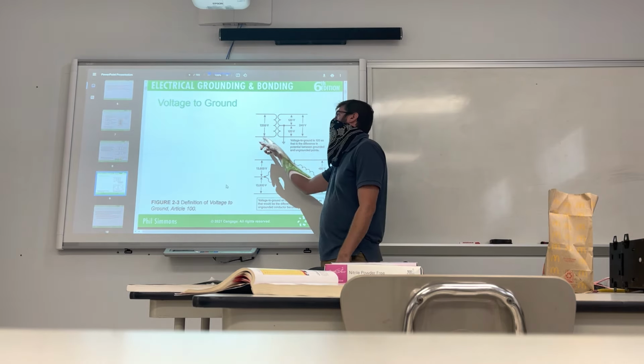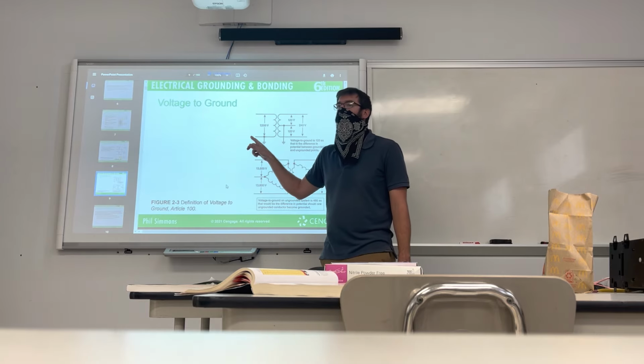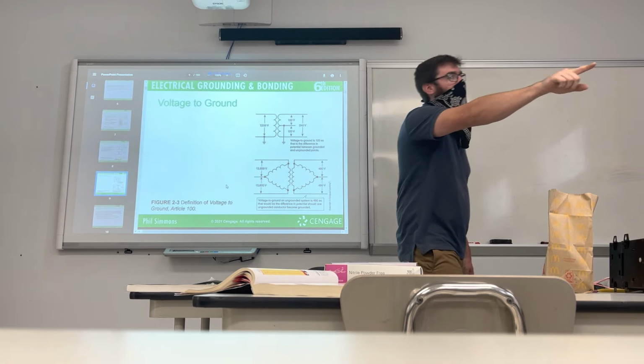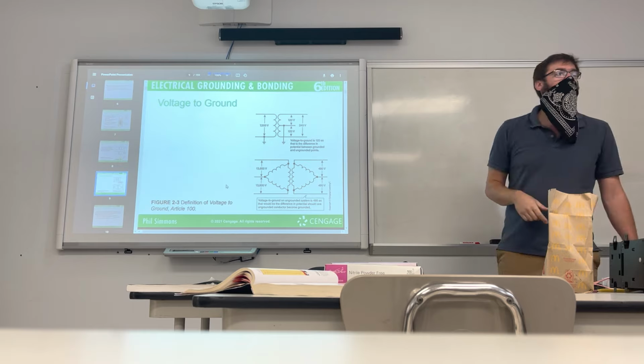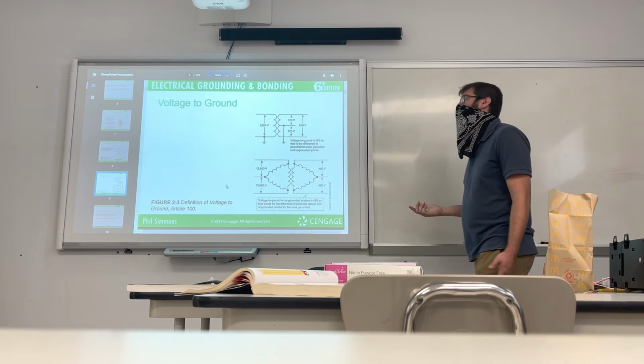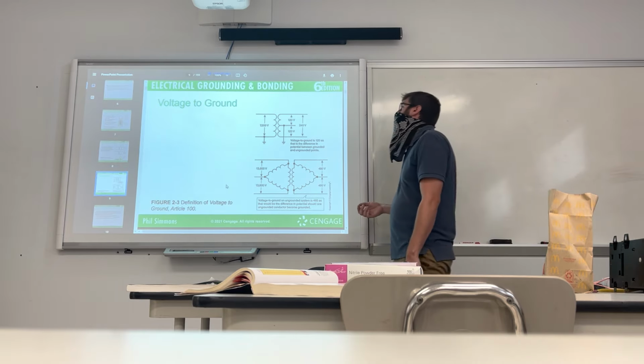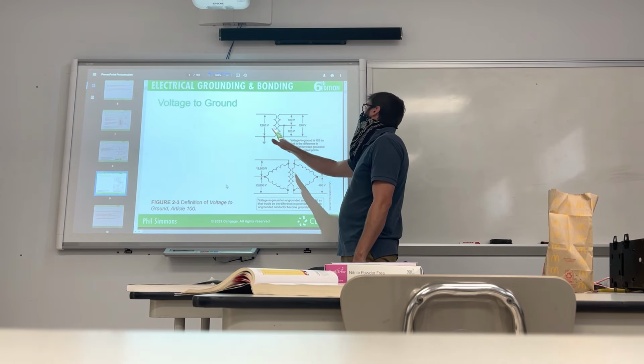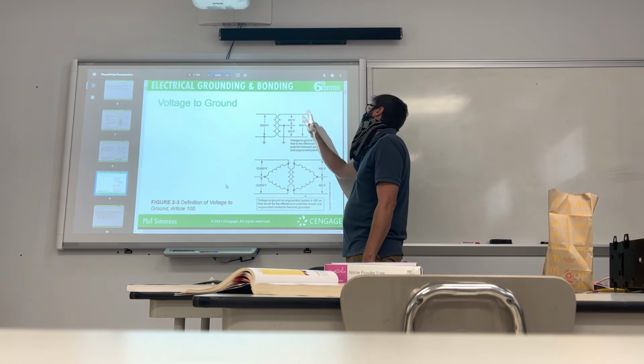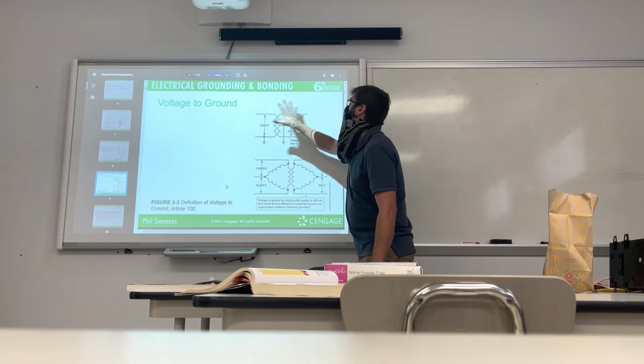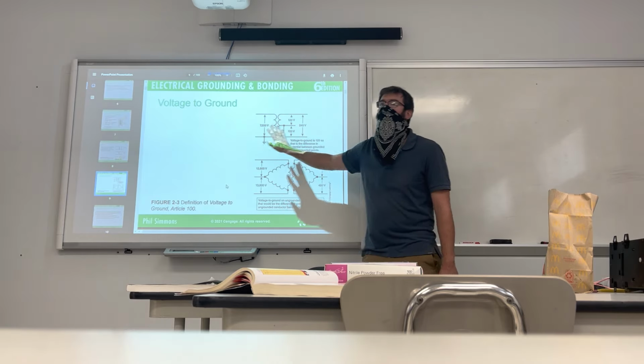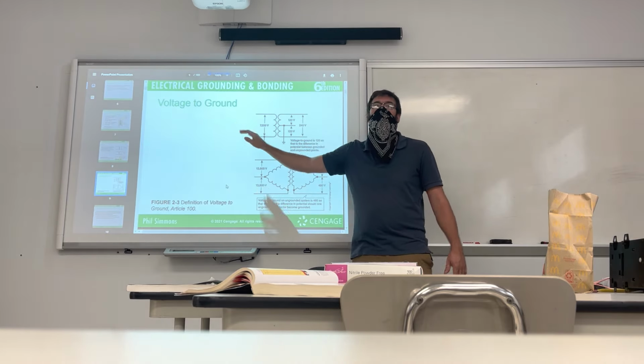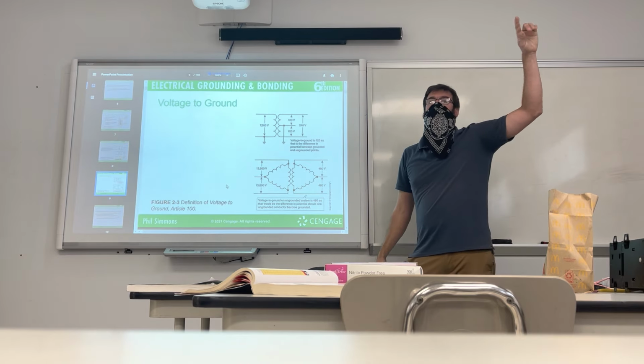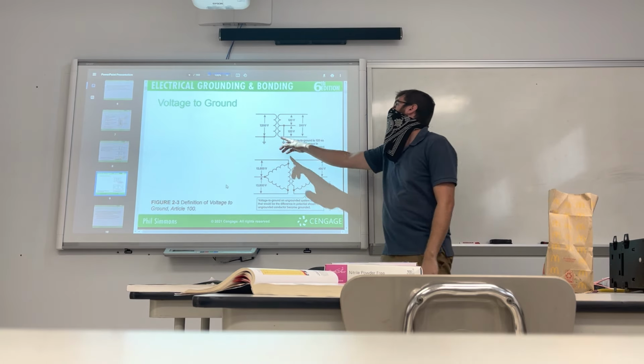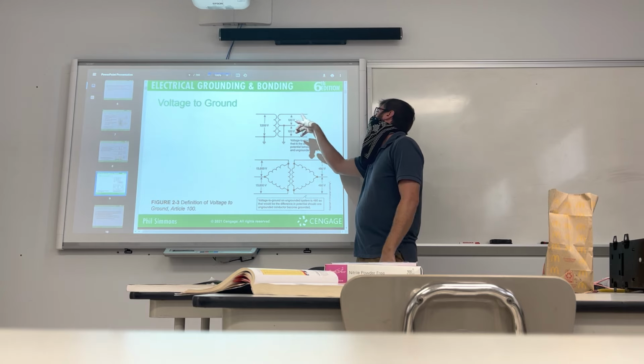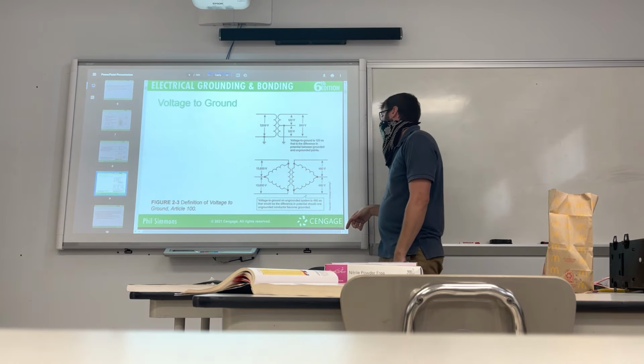Like I was just mentioning to Phil, on the street we have 7200 volts. In K, what's that called? 7.2 kV. Perfect. And that steps it down to 2 poles of 120. When you put them together, that's 240. This is common. This is what you see in every house. This is how they step it down. You only have one line coming down the street at 7.2 kV, and that's stepping it down to 2 legs of 120, or 240 from leg to leg.